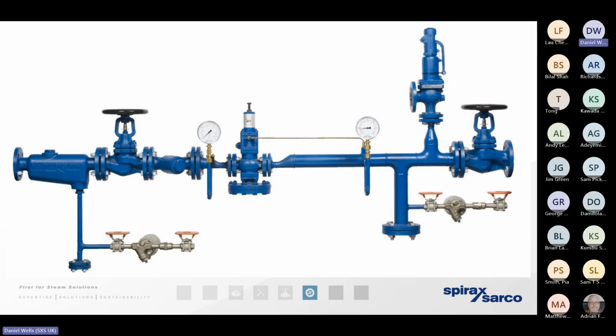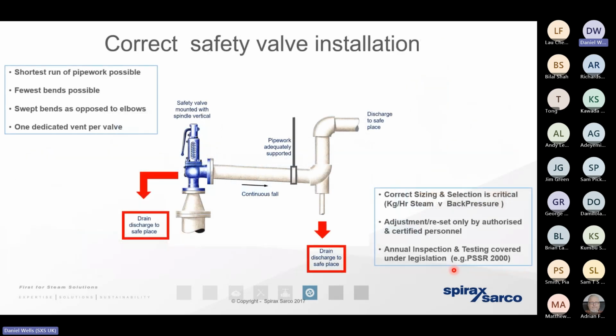Now, not every process will require a safety valve. If the heat exchanger is rated greater than the boiler pressure, a safety valve isn't going to be required. But when a safety valve is required, we need to have it correctly sized. It needs to be installed in the vertical without any isolation upstream or downstream. We need to have the appropriate drain points to ensure any steam that is weeping off the seats and condensing can be drained away. And we want to keep that run of pipework venting the steam away to the absolute minimum so there isn't an unnecessary back pressure there.